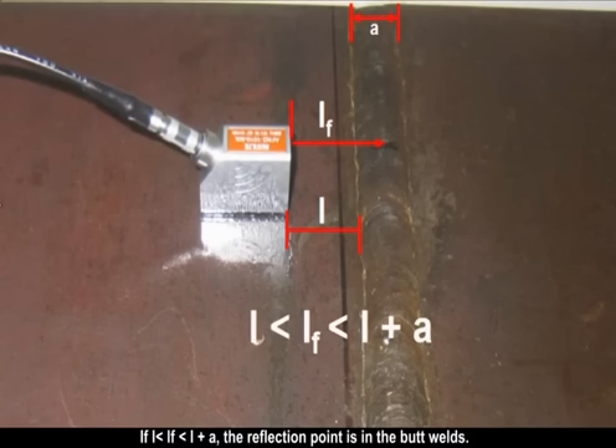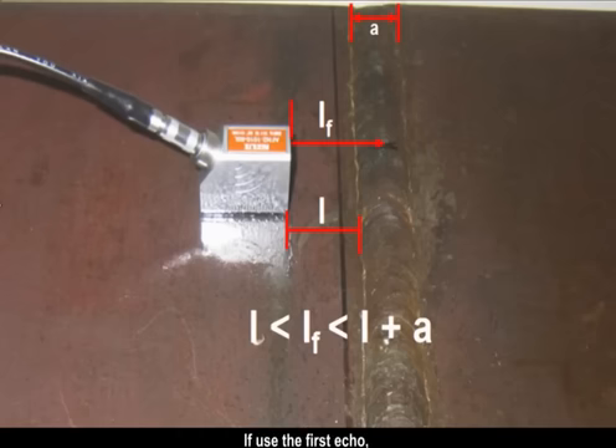If L is less than LF, and LF is less than L plus A, the reflection point is in the butt welds. If using the first echo, the distance between the reflection point and the steel plate surface is less than the steel plate thickness, so it can be considered as defect reflection.